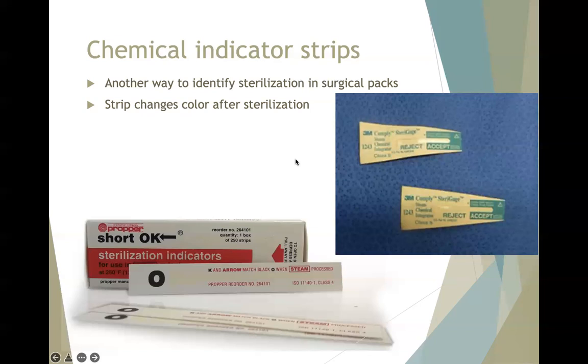We can put it right on the trays of the autoclave, or we can put it inside of our packs, which is kind of the most common method, is to put one inside of every pack, because even if the indicator tape changes color, that really only means that it was able to penetrate the outside of the pack, not necessarily that it got all the way to the inside. So we usually will put one of these OK strips right into that pack before we wrap it up in the drapes. But you can also just put it right on the racks in the autoclave. And it's going to be kind of up to your clinic and what their protocols are for their sterilization process.